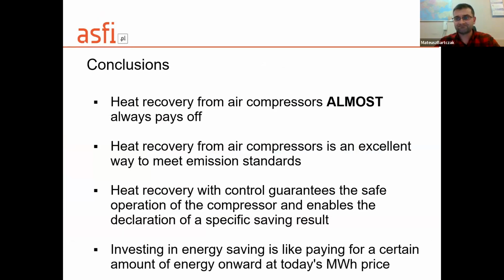Conclusions. Heat recovery from a compressor almost always pays off. It's an excellent way to meet emission standards and reduce footprint. Heat recovery with control guarantees the safe operation of the compressor and enables the declaration of a specific saving result.